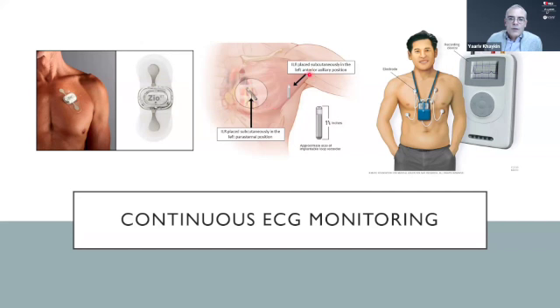We do have the option of implantable monitors. Implantable monitors sort of also look like little USB sticks. They have electrodes at either end of the device with a battery and a computer inside. It records the ECG continuously, but it doesn't keep all of that information. It records and erases typically about a 2-minute window. And if certain conditions are met, like it detects that your heart went too fast, too slow, had an irregular pattern, or if you activated it with a remote control, it would remember that 2-minute window until the memory banks are cleared.